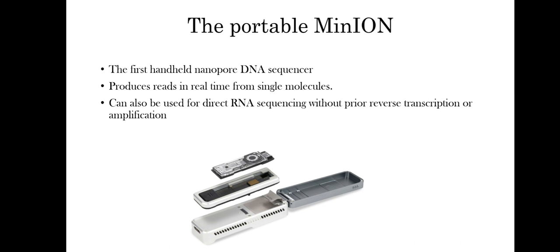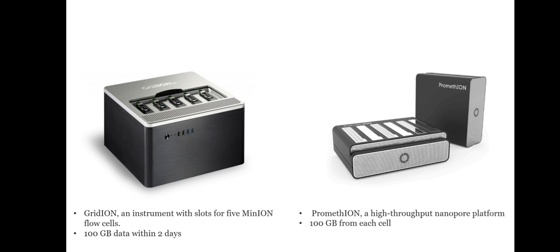The first handheld nanopore DNA sequencer is the portable MinION. It produces reads in real time from single molecules and can also be used for direct RNA sequencing without prior reverse transcription or amplification. Following the introduction of the MinION, there was the release of GridION, which is essentially an instrument with a slot of five MinION flow cells and an integrated computer for base calling. 100 gigabytes of data can be obtained within two days.